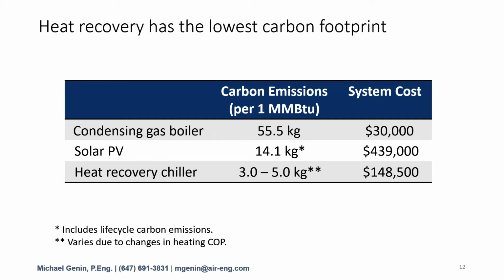Also to note, the range in carbon emissions from the heat recovery chiller is mostly dependent on the COP you achieved, which is mostly dependent on the design hot water temperature as we illustrated. In most cases, the heat recovery chiller has a lower carbon footprint and a lower installed cost. It doesn't mean that it's always better than solar PV, or that no one should ever use solar PV. But what it does mean is that if you have a relatively clean electric grid, your first line of defense for future greenhouse gas emissions should be heat recovery.